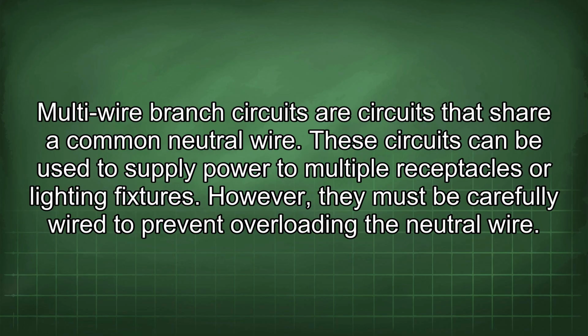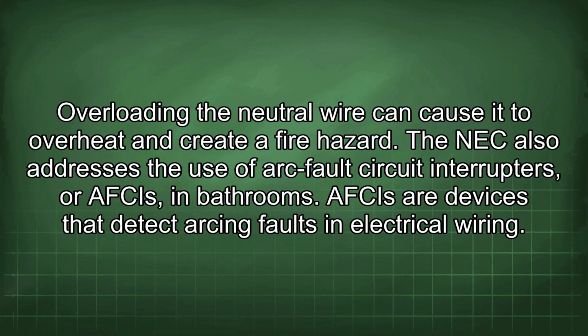Multi-wire branch circuits are circuits that share a common neutral wire. These circuits can be used to supply power to multiple receptacles or lighting fixtures. However, they must be carefully wired to prevent overloading the neutral wire. Overloading the neutral wire can cause it to overheat and create a fire hazard.